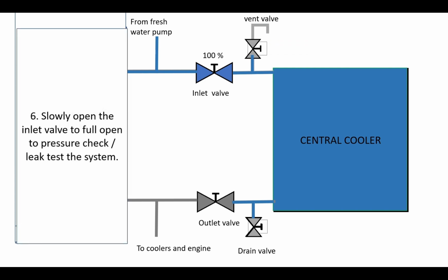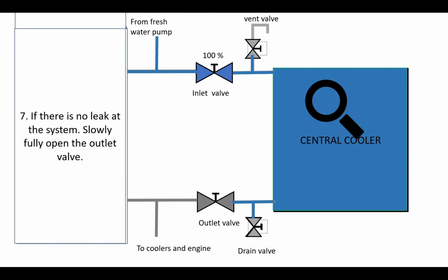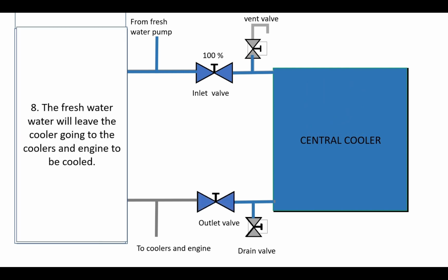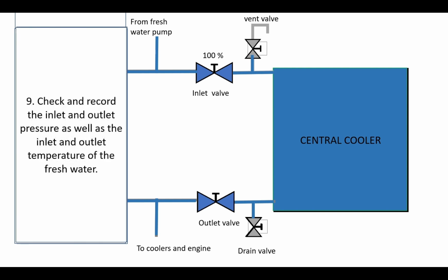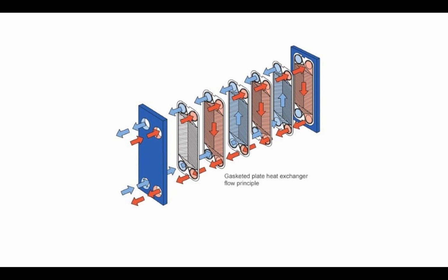Slowly fully open the inlet valve and pressure check the system by checking for leaks. If there is no leak in the system, slowly open the outlet valve. The fresh water will then leave the cooler and go to cool other heat exchangers and engines. Check and record the pressure as well as the temperature for reference. Now that seawater and fresh water are filled, the central cooler is in service.